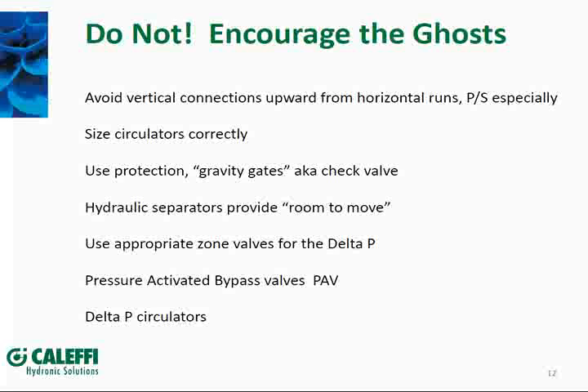There are different types of zone valves with different shutoff pressures. If you have a pump developing high delta P, you must select a zone valve that can shut off against that pressure. For a commercial building with a pump developing 30–40 pounds delta P, a zone valve rated at only 20 pounds shutoff will have bleed-through. We offer zone valves that can shut off against 75 pounds pressure — select the right valve for the application.